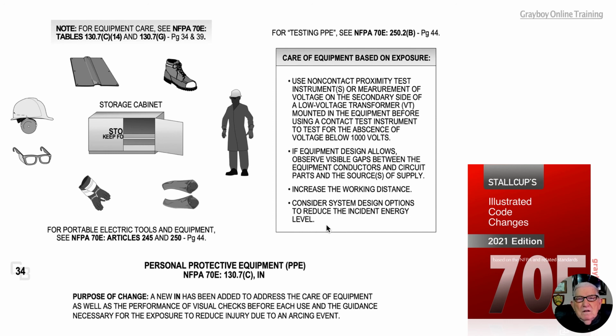And then we know we can review the Annex O and the Annex Q in 70E and find out a lot more about system design options that would reduce incident energy level due to the type of design that we would design and install to protect maintenance electricians performing a certain task on electrical equipment. And that's what this illustration is all about, making sure that the PPE will provide the protection that is needed to protect all the members of the body while performing a certain job task due to a condition where electrical arc could occur.